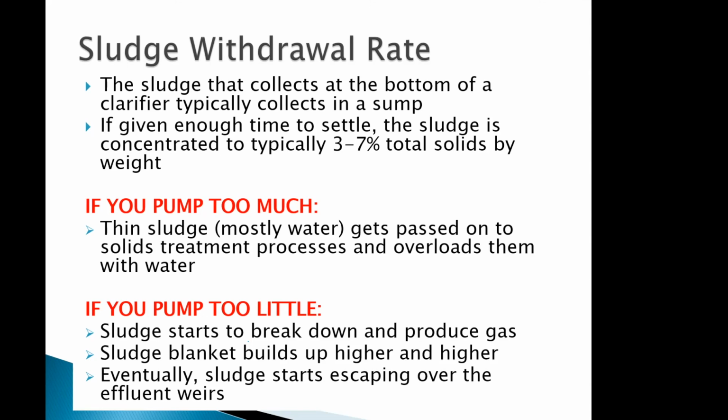So we're going to have some sort of sludge pumping that will pump the settled sludge out from the bottom of the tank. And there's a lot of questions, a lot of math that could be tested on sludge withdrawal rate. So this is something I would suggest you spend a little time on in your preparation. Generally, when that sludge settles, it's going to get scraped, either in a round clarifier, where a circular mechanism will scrape it to the center, or in a rectangular clarifier, where there'll be a chain and flight system that scrapes it all back into a pit or a hopper. So that sludge is going to be collected somewhere, and we're going to pump from that sump or hopper onto wherever it goes next. Could be a digester, it could be a drying bed, could be a dewatering process.